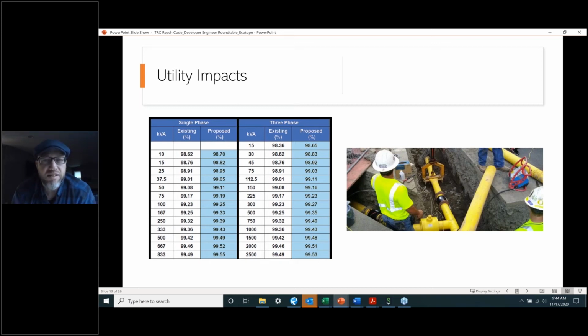The other part is your transformer size. I've heard a lot of folks talk about how going to heat pumps is this huge transformer bump, and I have not seen that. If you're right-sizing these things, the most I've ever seen is you bump up one class, but not a tremendous bump. Typical buildings, 1500 kVA might jump up to 2000. But you do have to plan around that, for both your peak heat pump load and your peak backup resistance, whatever strategy you use there.